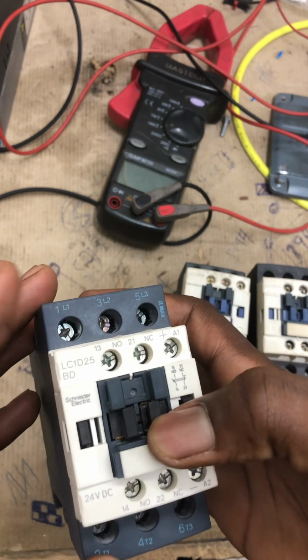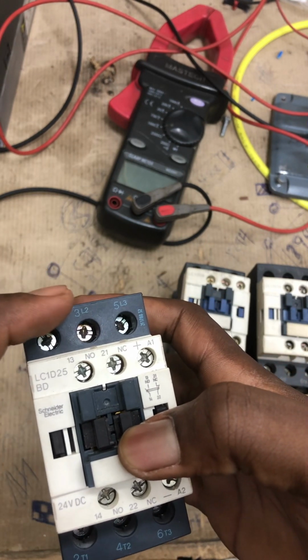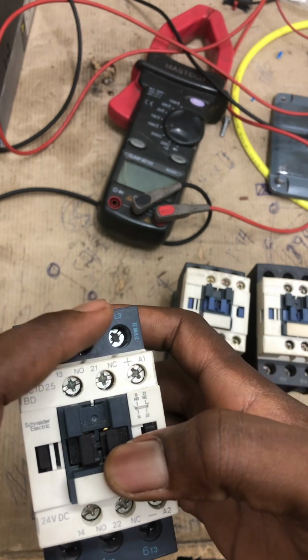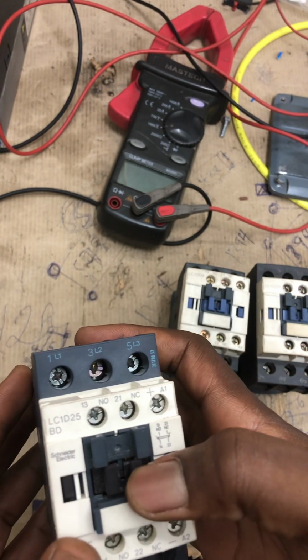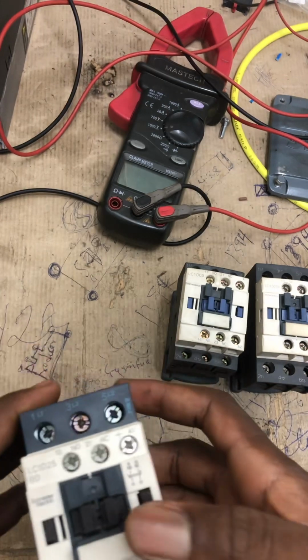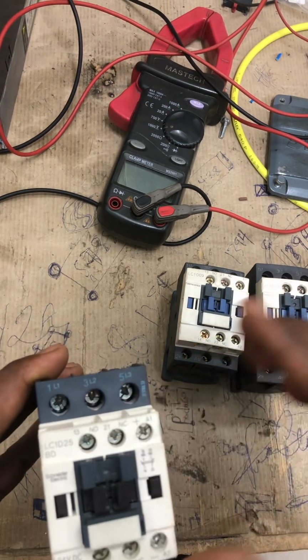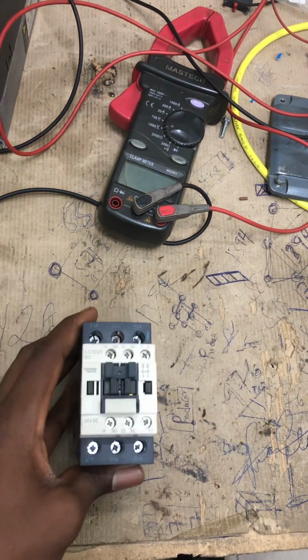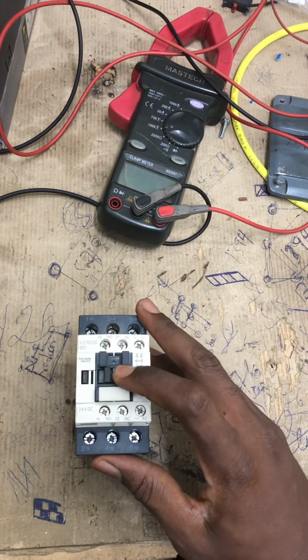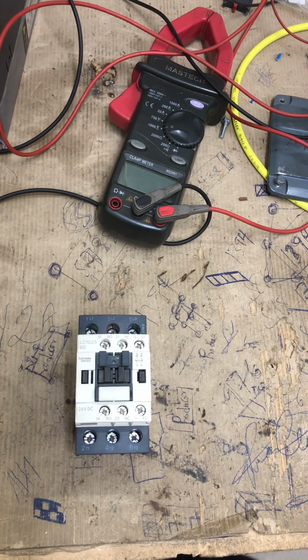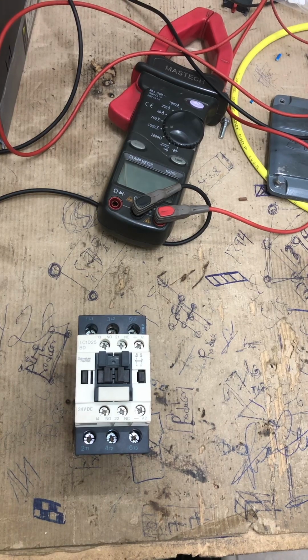1 and 2 become closed, 3 and 4 become closed, and then 5 and 6 become closed. They are the main lines. So I'll try and energize this contactor and then let's see. But before that, I'll have to test with a meter so that we know the state of the contactor.